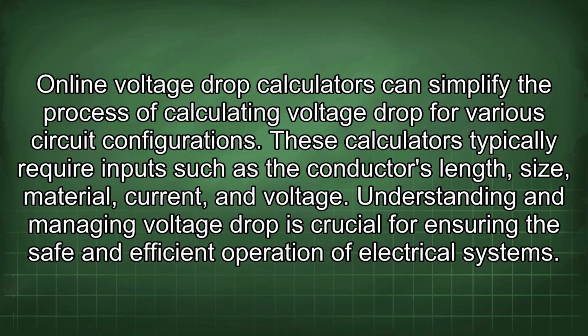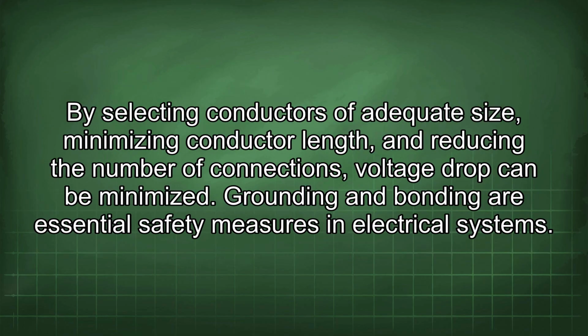Online voltage drop calculators can simplify the process of calculating voltage drop for various circuit configurations. These calculators typically require inputs such as the conductor's length, size, material, current, and voltage. Understanding and managing voltage drop is crucial for ensuring the safe and efficient operation of electrical systems. By selecting conductors of adequate size, minimizing conductor length, and reducing the number of connections, voltage drop can be minimized.